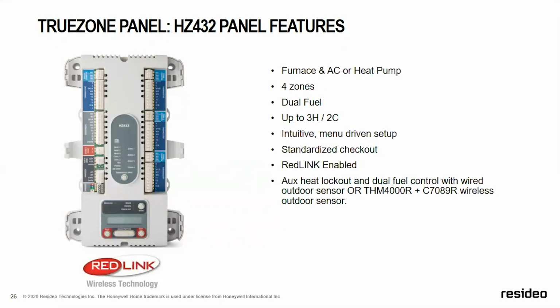This is a great panel because you can have this panel running a heat pump, use a standard thermostat, and it will do the conversion for you. As you know, on a heat pump, you're only doing Y1, Y2. If your thermostat's calling for W, this panel will convert that and call your heat pump. This is a great panel.